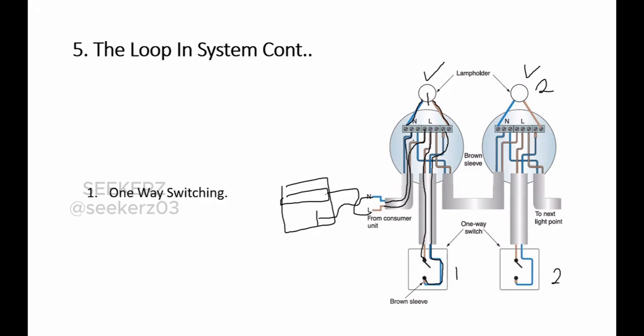Then we loop the wiring to the second lighting point. From the loop terminal we take the phase conductor and connect it to the loop terminal of the second ceiling rose. We also take the neutral conductor from the consumer unit and connect it to the neutral terminal of the second ceiling rose. Then the same wiring is done: we connect it to the second switch and the other side to the switch terminal, and from there we connect it to the second lamp.